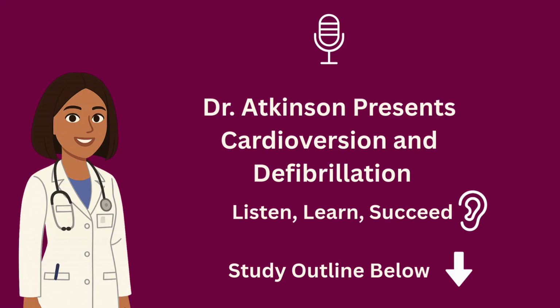If the first cardioversion attempt fails, remember that many machines automatically reset to unsynchronized mode, so the synchronizer must be reactivated. When cardioversion is elective, for example with atrial fibrillation lasting longer than 48 hours, anticoagulation for several weeks beforehand may be needed to reduce the risk of thromboembolism. Digoxin is usually withheld for 2 days before the procedure. The patient is kept NPO for at least 4 hours. Pads are typically placed in anteroposterior position, and the patient receives moderate IV sedation, oxygen support, and monitoring throughout. The shock voltage may range anywhere from 50 to 360 joules, depending on the defibrillator and the patient's condition. Success is indicated by return to sinus rhythm, stable blood pressure, and strong peripheral pulses. Afterward, airway management, oxygen monitoring, and vital signs remain nursing priorities until the patient is fully recovered from sedation.